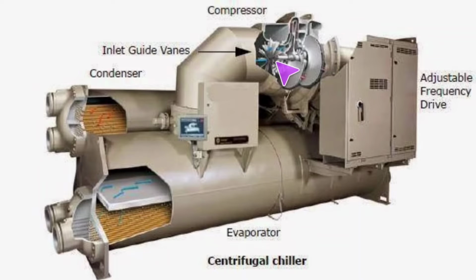So at the startup of this machine, these guide vanes are going to be in full closed position. If they're not, you're going to have issues. More specifically, the main issue that usually happens is the compressor will overamp at startup. So when it goes to turn on, it will overcurrent, and it's going to give you problems there. And that could be because, say, there's a dozen vanes in there, and one of them, the armature just breaks. Well, when the armature breaks, it'll get stuck in a single position. Maybe it won't close like it's supposed to all the way, or something along those lines. When that happens, that's what you're going to have.